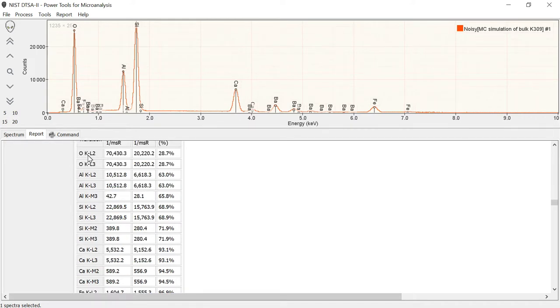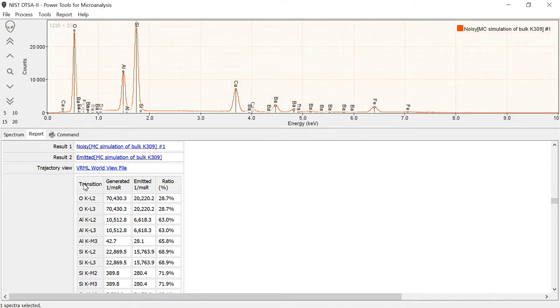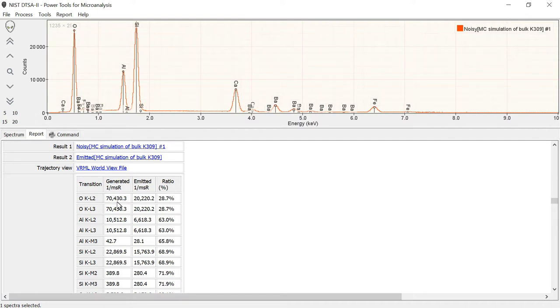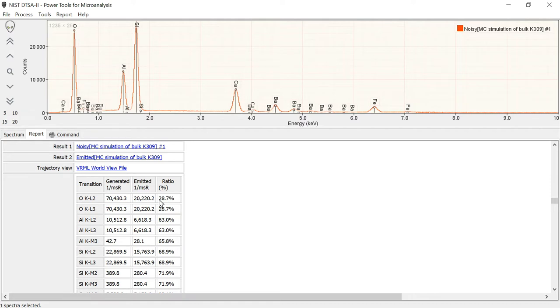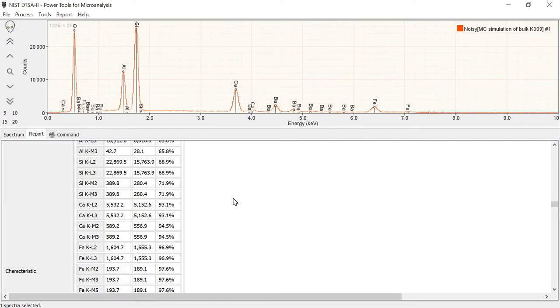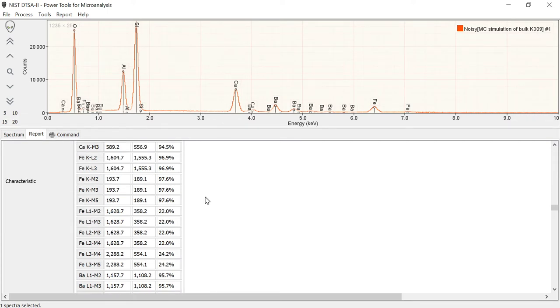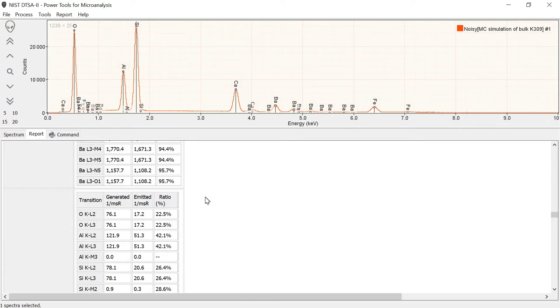Then we get some data out. These are the transition, the number of x-rays generated per millisterad. And then the number that are actually emitted. So the generated is the number that are actually produced in the sample. The emitted are the number that actually emerge out of the sample. And then the ratio. So this is what fraction of those that are generated actually make it out. It turns out that 100% minus 28.7% of the oxygen is absorbed. So about 71.3% of the oxygen actually never makes it out of the sample. So that's useful information. It gives you an idea of what's going on in the sample. We have the data for lots of different elements and lots of different lines in those elements. So this is the characteristic x-rays.